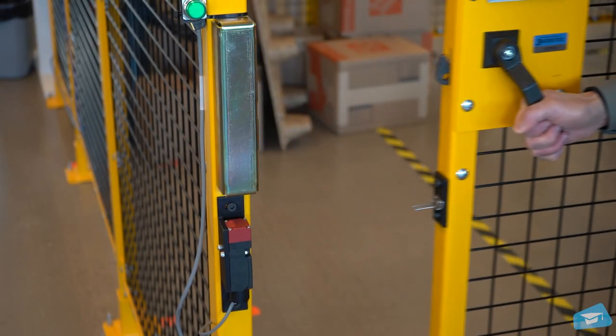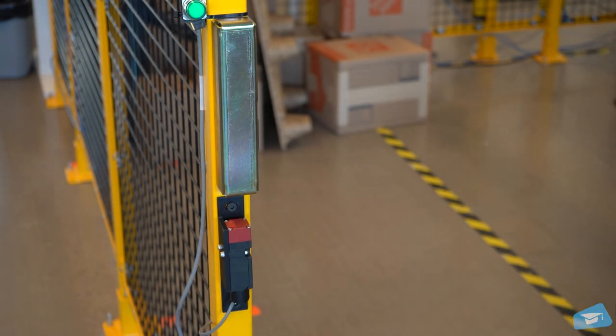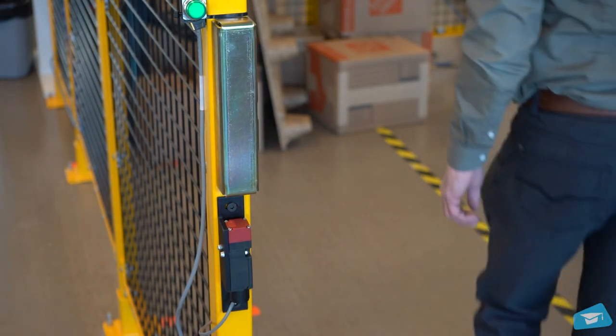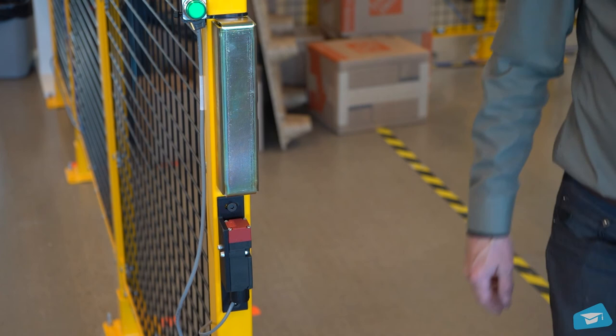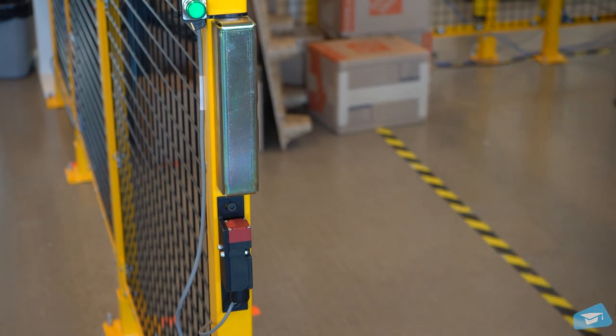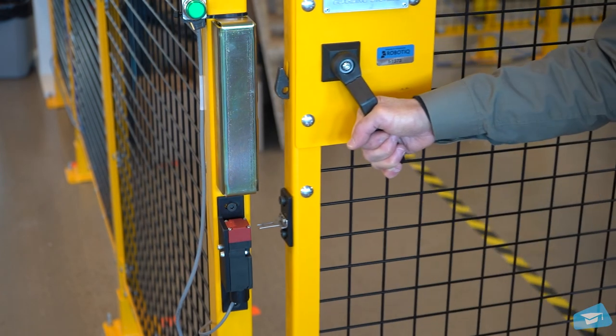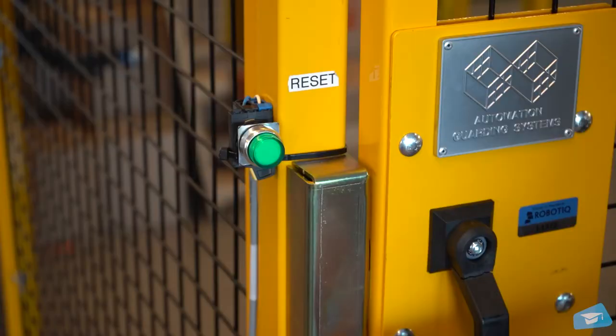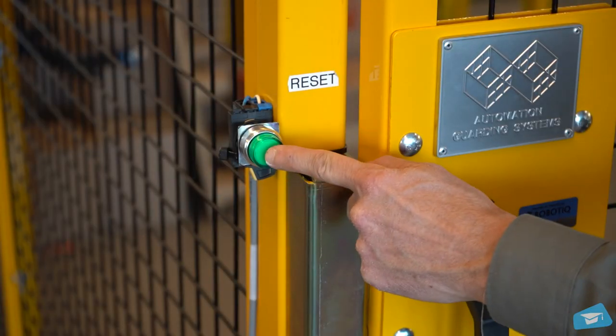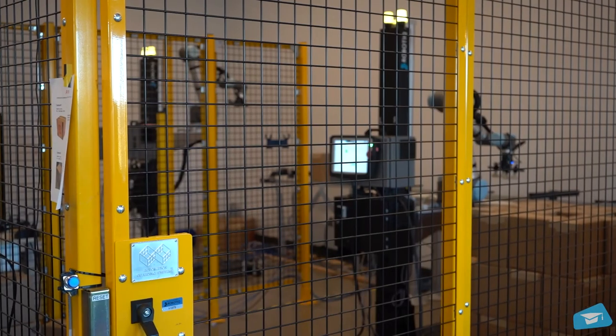In down-to-earth language, this means that when the operator comes in, the cell will stop. When he is done with the pallet change, the operator needs to exit the cell. The cell will restart automatically if safety scanners are used. If light curtains or safety interlocks are installed, the cell will need a manual restart. This restart can be a green start button on the outside of the cell, for example.